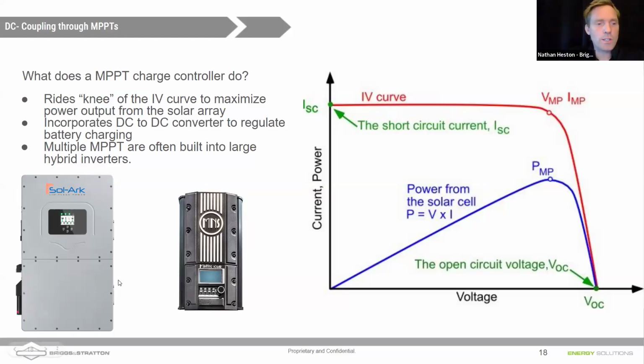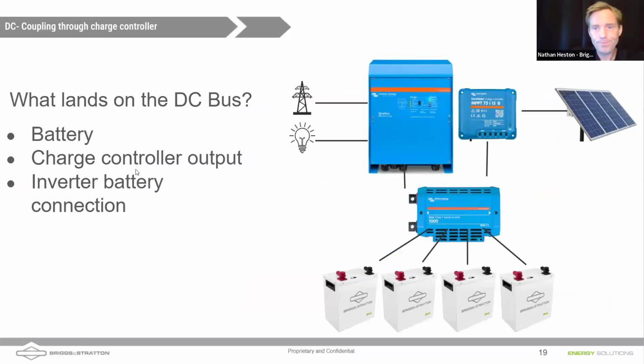Well, the Sol-Ark that you can see on the screen there, that's got built-in MPPTs, right, Daniel? And I believe that's a 15K, and that has 3 independent MPPTs built into it, each one capable of 7.5 kilowatts of power. Now, the full output power of the Sol-Ark, or full input from solar, will be limited to 15K. That's the nameplate rating on the inverter. But you can oversize your solar arrays, and you can oversize those solar arrays so that you get something called inverter clipping, right? Which will allow you to pull 15 kilowatts earlier in the day, etc. So anyway, the Sol-Ark has these built in.